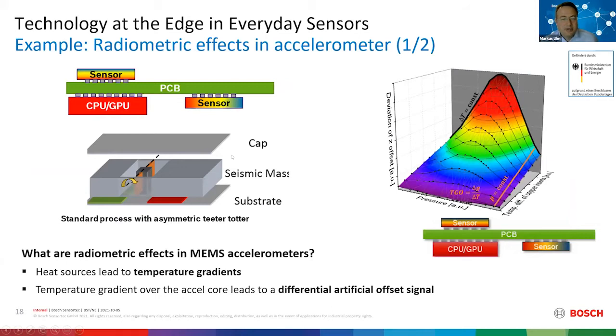That's quite a challenge if you imagine it, but there's other things too that I think are truly challenging. If you look on a sensor here in an application, typically, as we will later on see, temperature changes and TCO calibration is an important topic. But not only that, you also have to deal with temperature gradients. Why is this? The temperature here is, of course, never homogeneous, and so you do have a certain temperature gradient over your sensor. And if you have an asymmetric sensor, like you typically use the teeter totter, for instance, in Z-channel things, there's different gas pressures or radiometric effects on the mass here, and you do see an offset as a consequence of this.